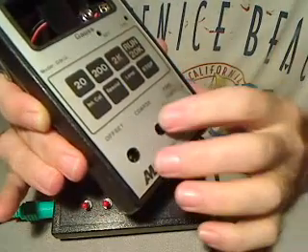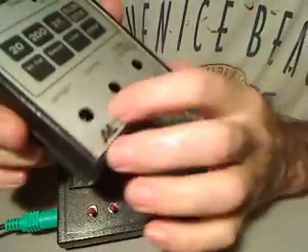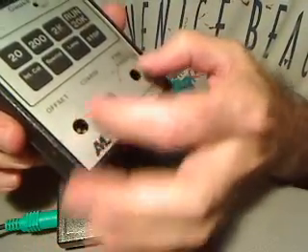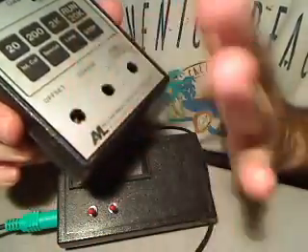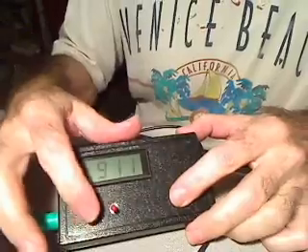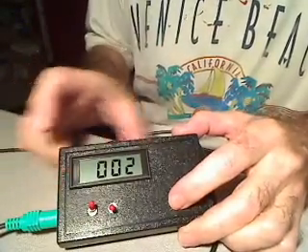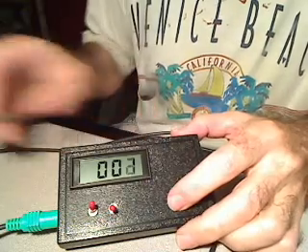Sometimes to really get it right, you might have to do that two or three times. The worst thing about this was those knobs were so exposed that any little bump would throw off your meter and you'd have to zero it all over again. That's why the new meter is nice — the calibration screws are concealed and can't be altered accidentally.